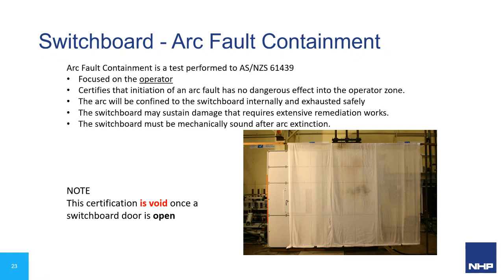An important note though is that this certification is void once the switchboard door is open. I was looking at a European study about arc fault occurrences, and it was saying that 65% of the time an arc fault occurred while somebody was working within a sub-assembly. That makes sense if you think about it, because it means that somebody's in there messing around with it and something happens. The likelihood of something suddenly occurring on a switchboard on a wall minding its own business is pretty low. So yeah, 65% of the time it was with somebody working in that area. It's some food for thought.